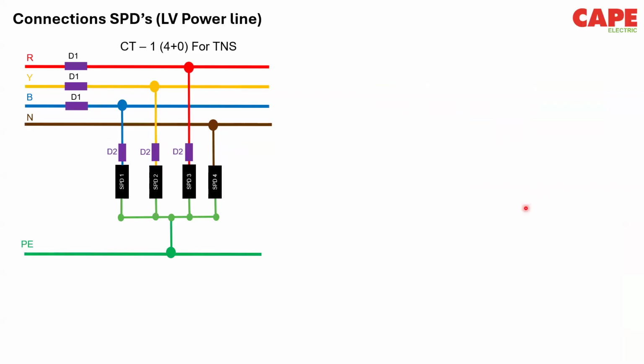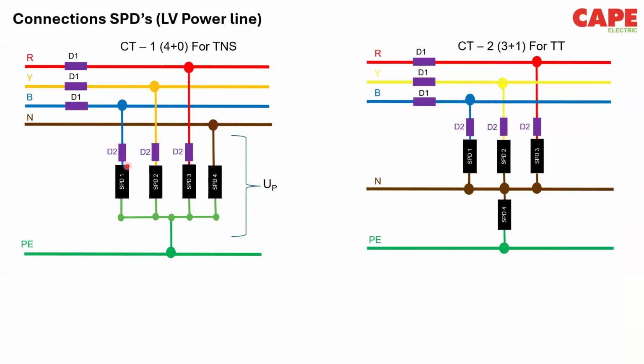Now, what is the advantage of having 4+0 is that UP is called the voltage protection level, and this UP is between the neutral and the PE. So it is just within the SPD. Okay.